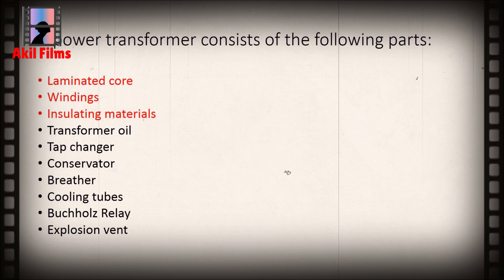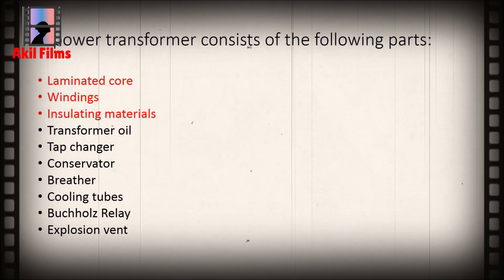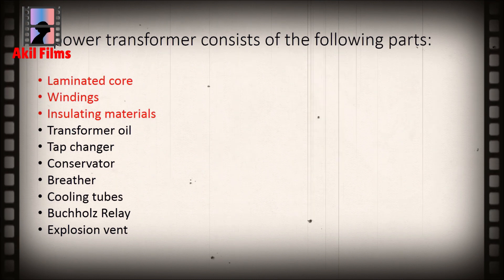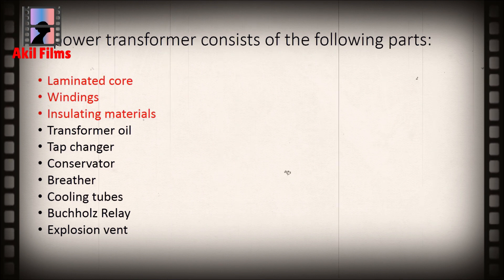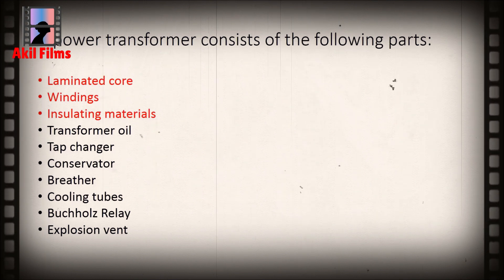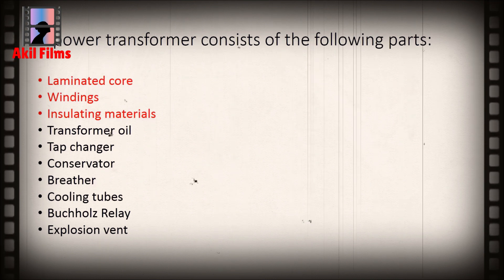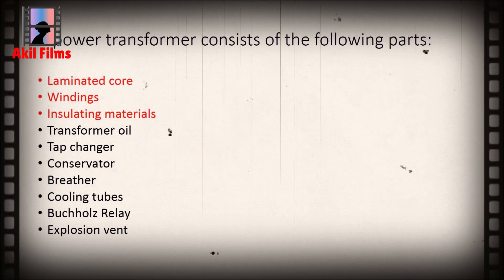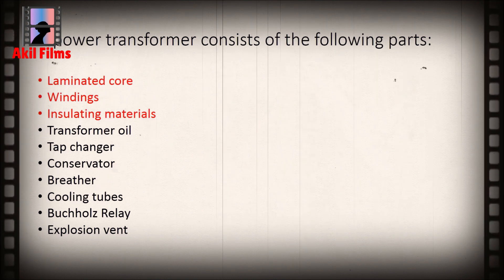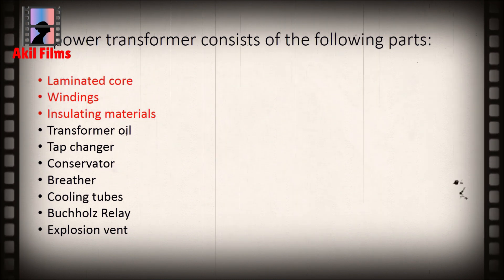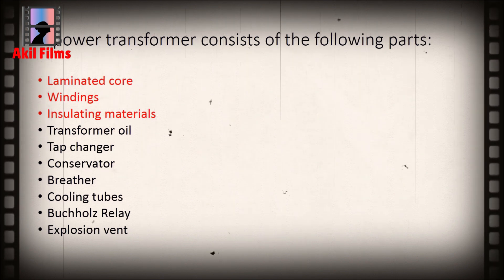A transformer consists of a laminated core, windings, insulating materials, transformer oil, tap changer, oil conservator, breather, cooling tubes, Buchholz relay, and explosion vent. Of these, the laminated soft iron core, windings, and insulating material are the primary parts and are present in all transformers, whereas the rest can be seen only in transformers having a capacity of more than 50 kVA.